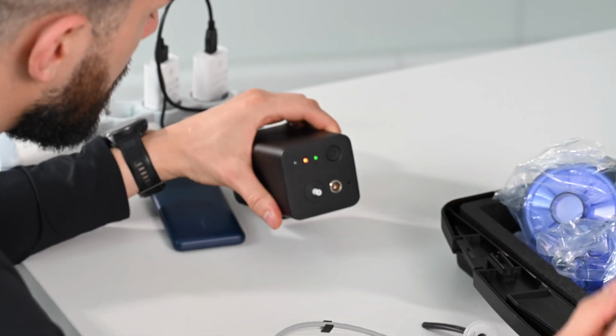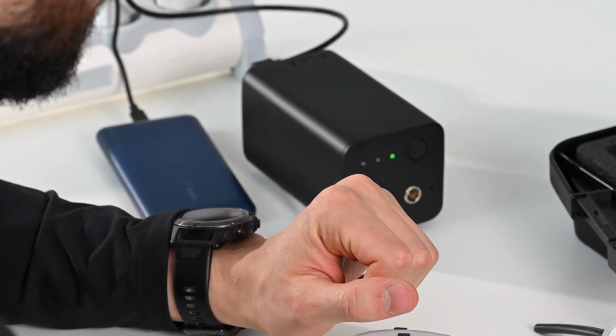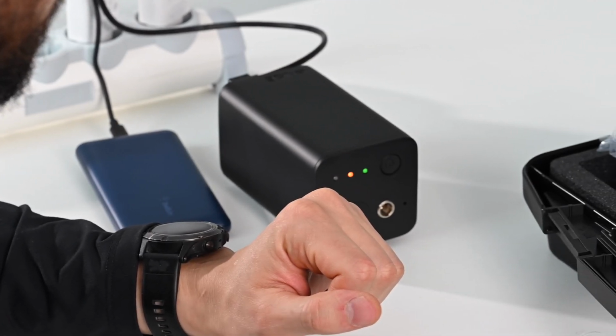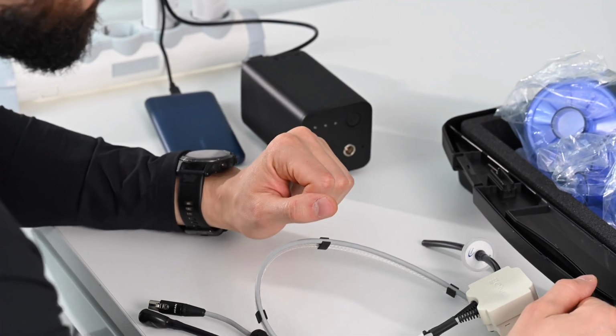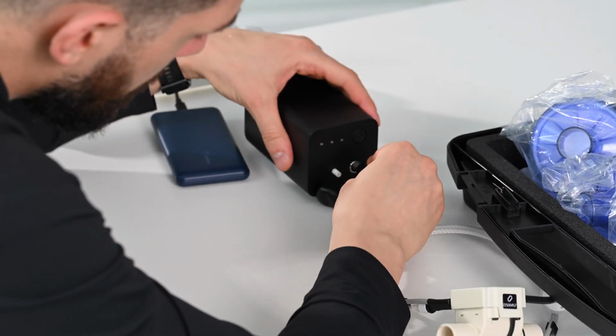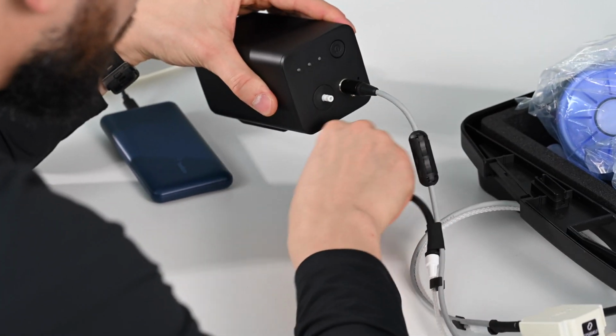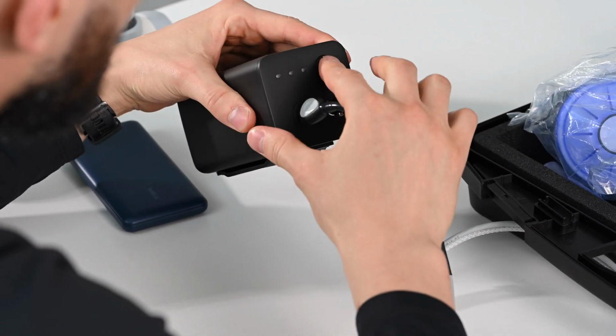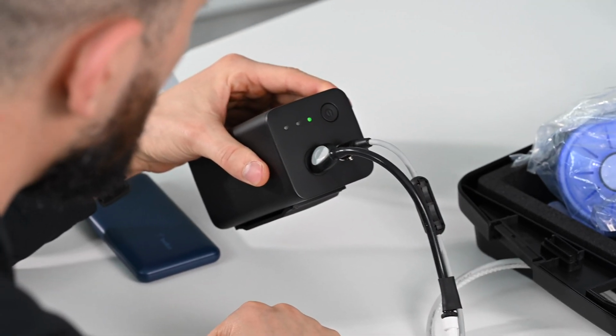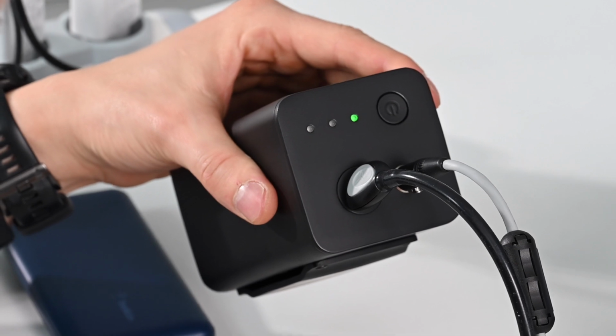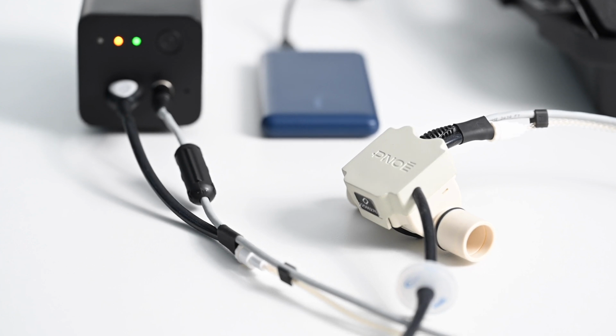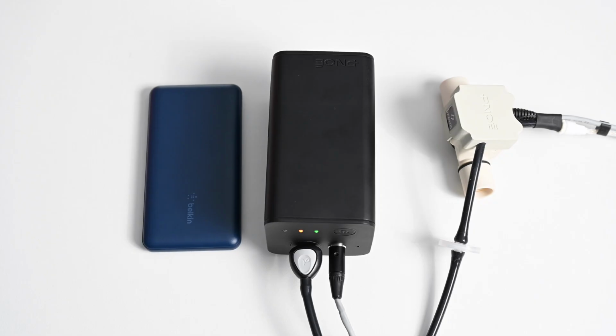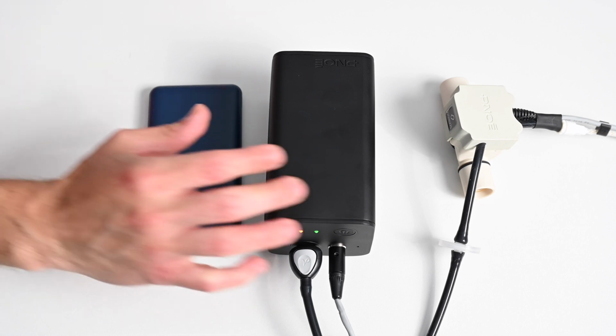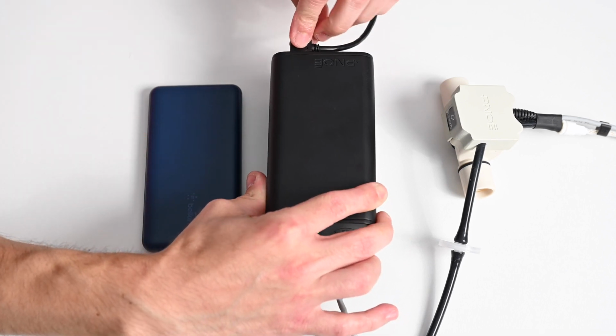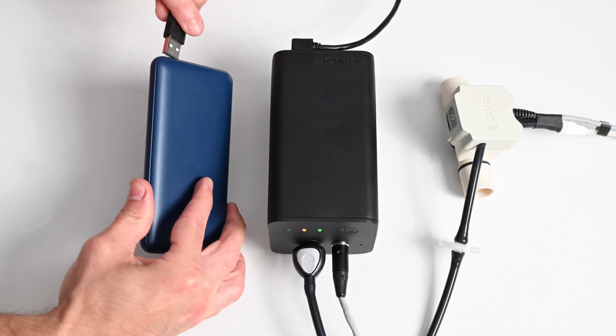In order to warm up the flow sensor, power the PNOE unit off. Then connect the 2 cables of the flow sensor, and then power the PNOE unit back on. Allow the flow sensor to warm up for 10 minutes before initiating the test. When conducting a test, always have the PNOE unit connected to the power bank that was provided in your kit. It is key to check that the power bank is turned on by checking the lights on the side of it.